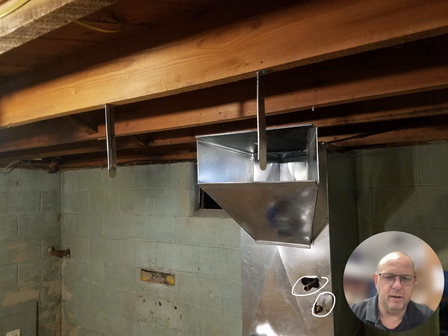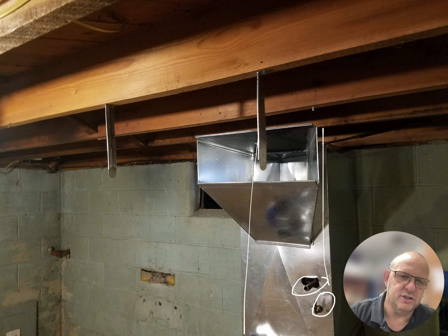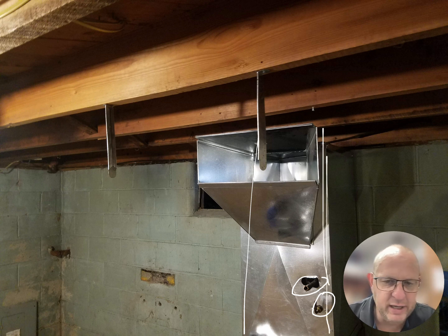They are going to be encased inside of that plenum itself. The plenum can extend off of the furnace as high as we'd like to run it, but there are limitations to the height of it. The further we get away from the furnace, the more dissipation of the static pressure, total pressure, and velocity pressure will happen. So we want to try to keep that plenum as short as we can get it within reason. I would say at least 3 feet off of the top of the evaporator, and then extending out into our trunks that are going to distribute that air into the places where we want to put that air.